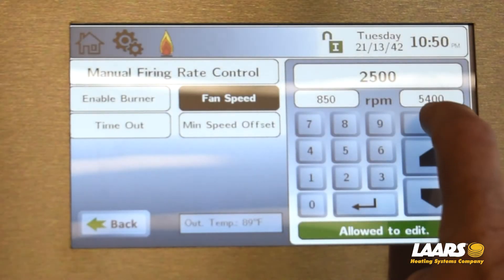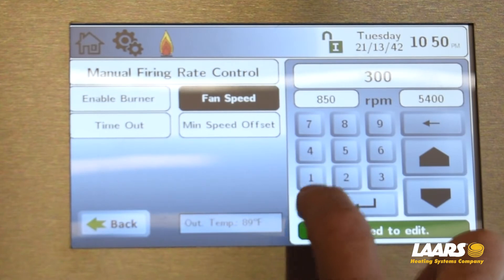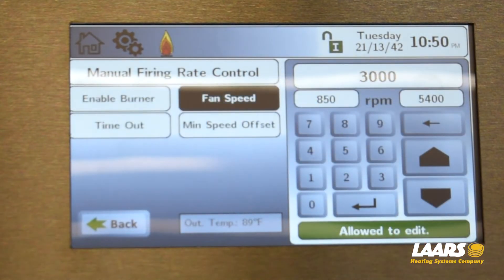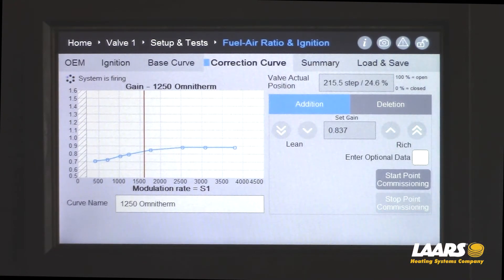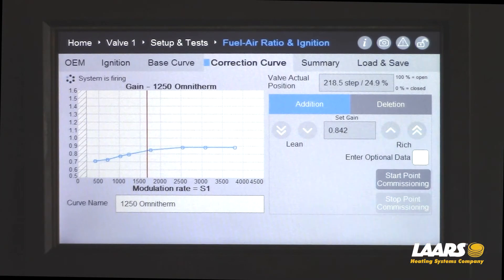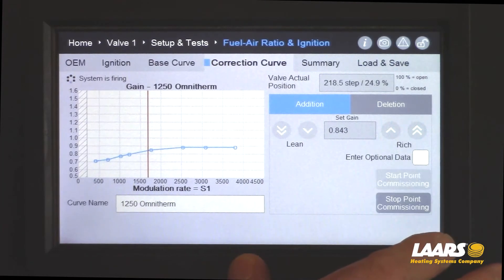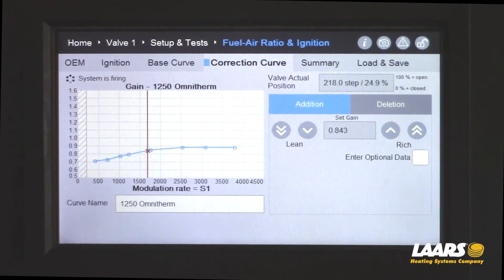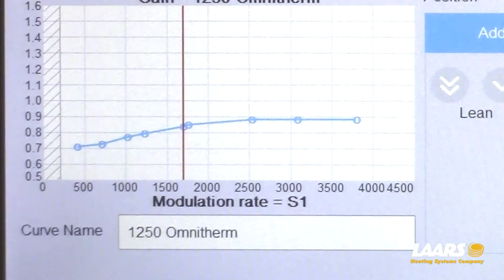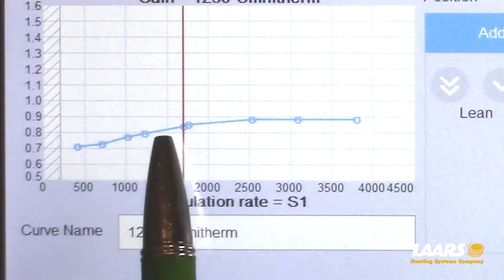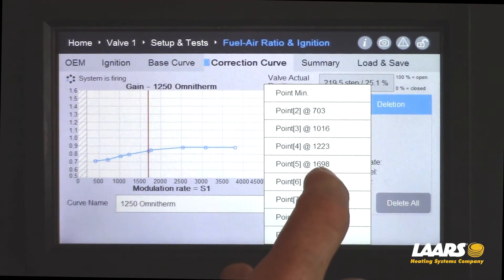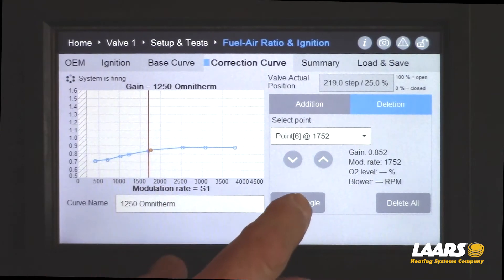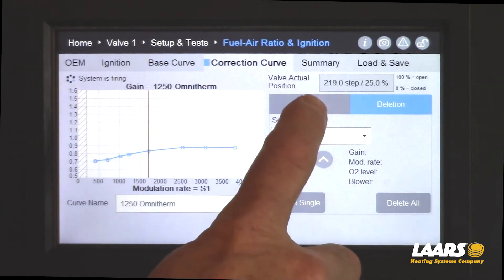Go back to the link display and choose 3000 RPMs. Wait for the indicator to come on and be patient with your analyzer — make sure we're around 8.5% CO2. Go by your combustion air temperature coming in. If you're dialed in, click start point commissioning and add another generic point. If a second nearby point appears, go to deletion, select one, and choose P6 to highlight it. If that's the correct point, click delete, then go back to addition.